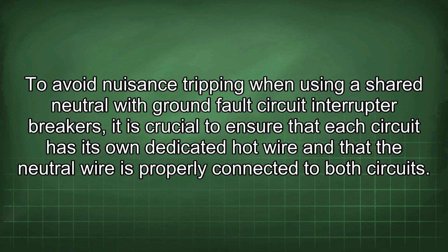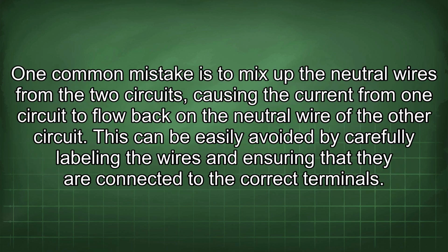To avoid nuisance tripping when using a shared neutral with ground fault circuit interrupter breakers, it is crucial to ensure that each circuit has its own dedicated hot wire and that the neutral wire is properly connected to both circuits. One common mistake is to mix up the neutral wires from the two circuits, causing the current from one circuit to flow back on the neutral wire of the other circuit. This can be easily avoided by carefully labeling the wires and ensuring that they are connected to the correct terminals.